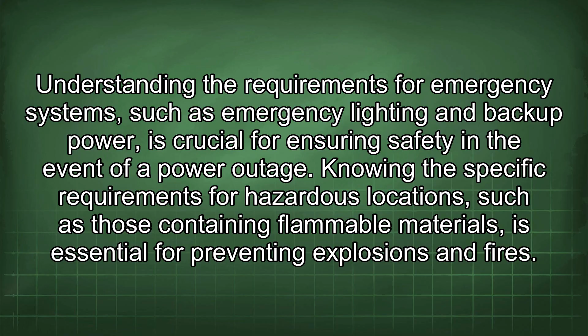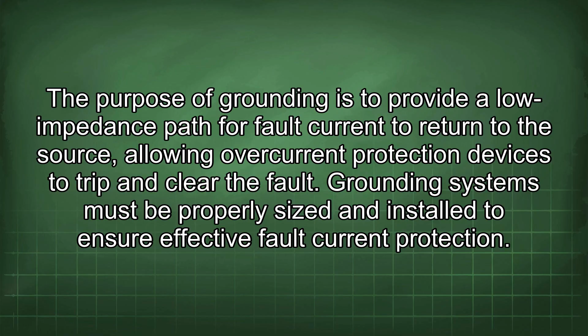The purpose of grounding is to provide a low impedance path for fault current to return to the source, allowing overcurrent protection devices to trip and clear the fault. Grounding systems must be properly sized and installed to ensure effective fault current protection.